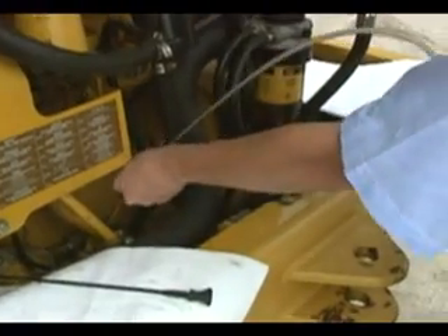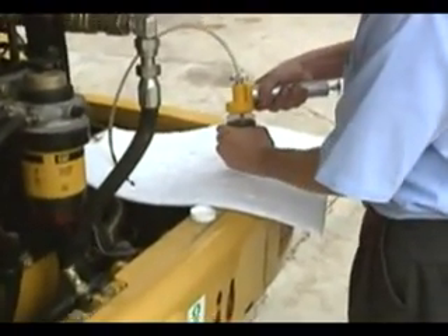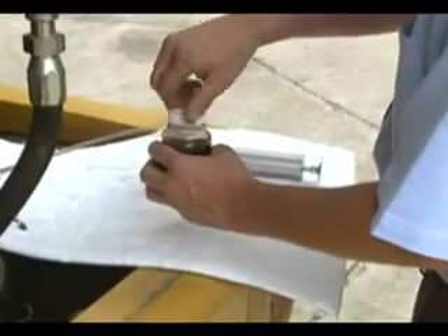Take the tubing out of the compartment. Then remove the bottle from the vacuum pump and secure the cap. The outside of the tube and the underside of the vacuum pump head should be free of oil.